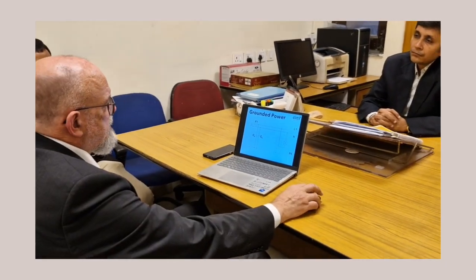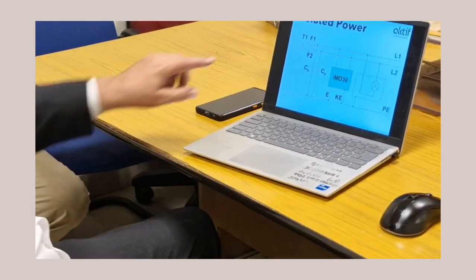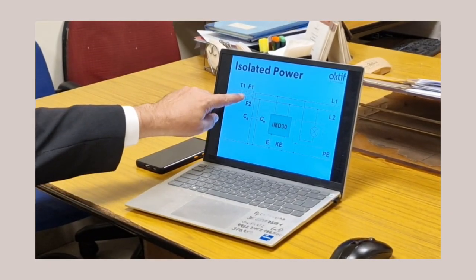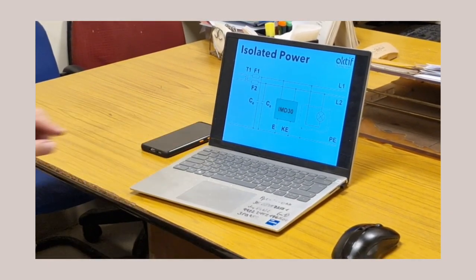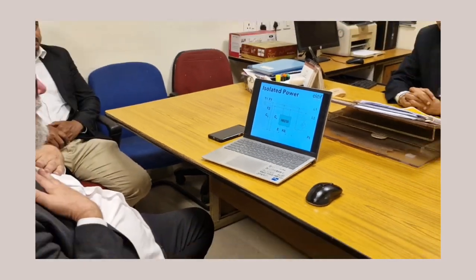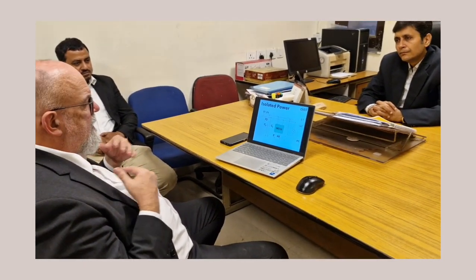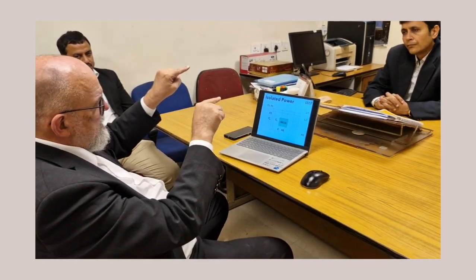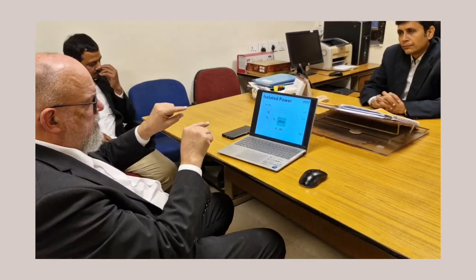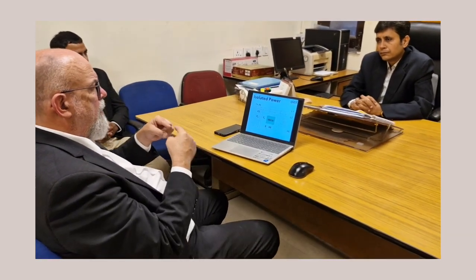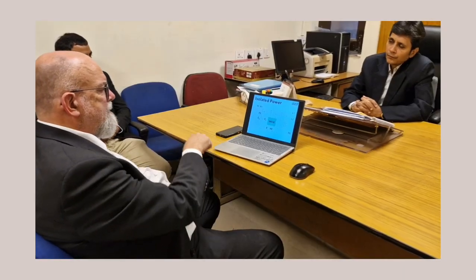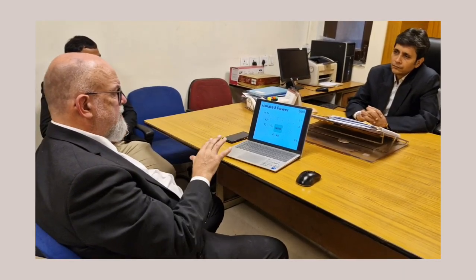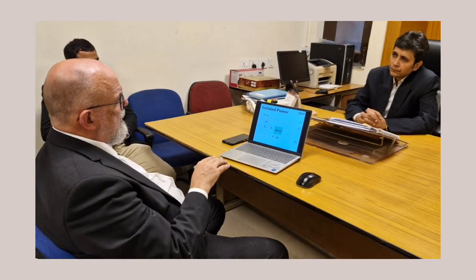In this case, we use isolated power, where there is no connection between the secondary side and the ground. The only connection there is our IMD, insulation monitoring device. It is connected to both supplying lines, 230 volt, L1, L2, and then connected to the ground, and it continuously monitors the electrical system where it's connected. The maximum size according to the standard is 10 kVA, so that the leakage current could not become very high.